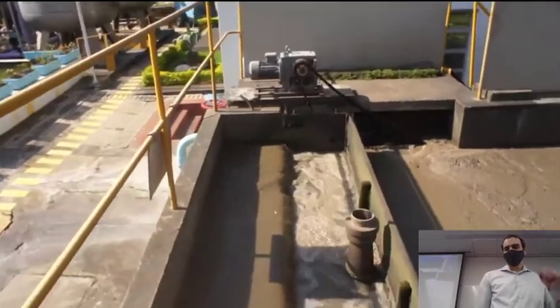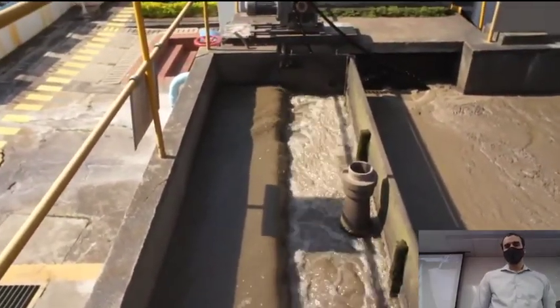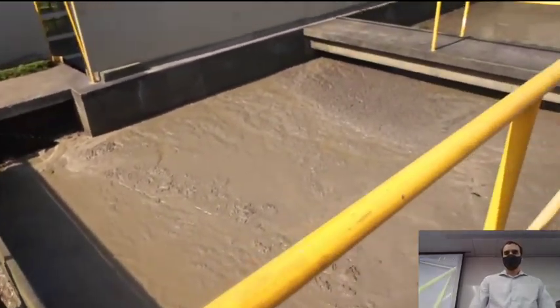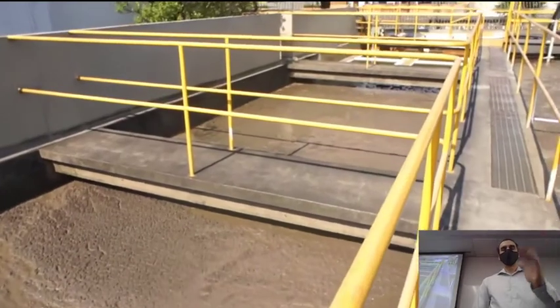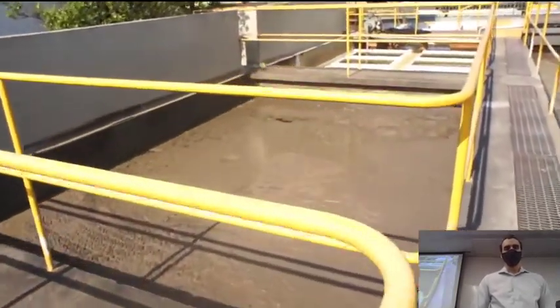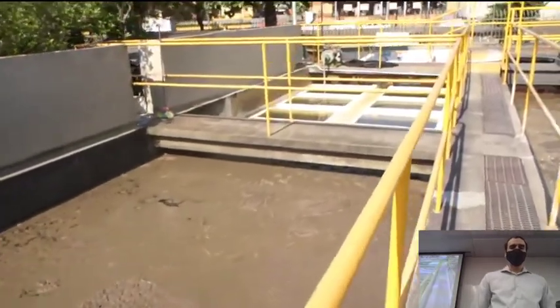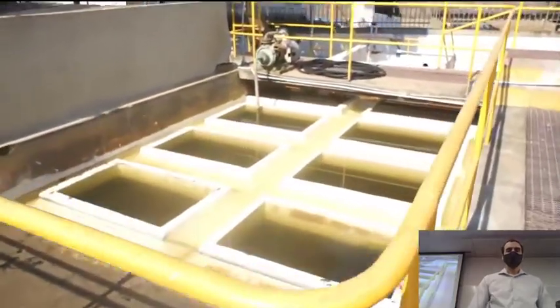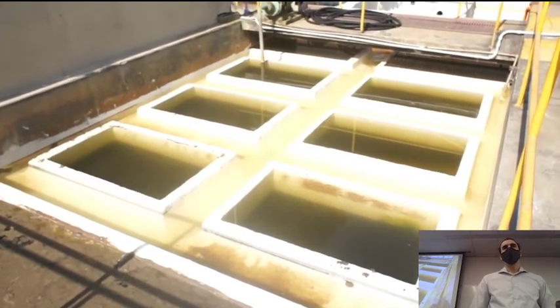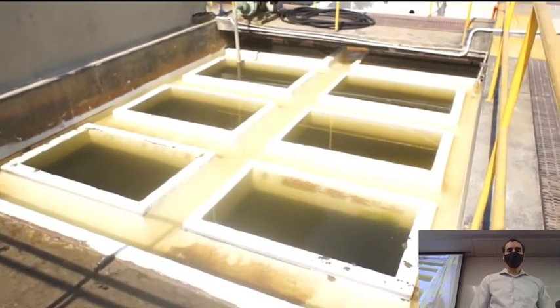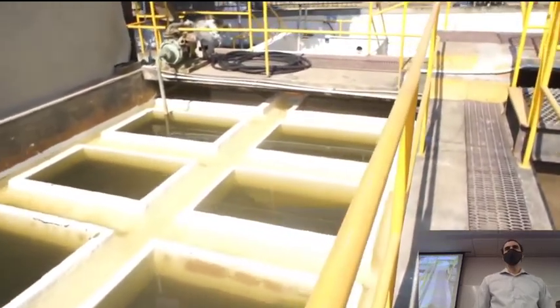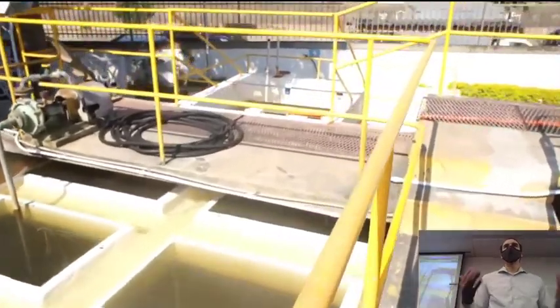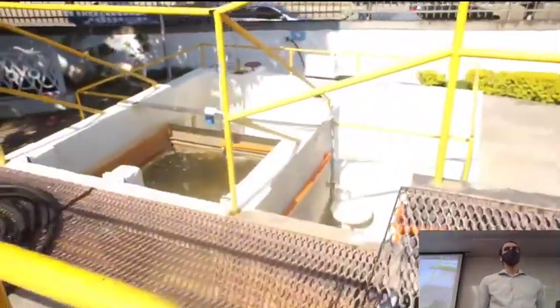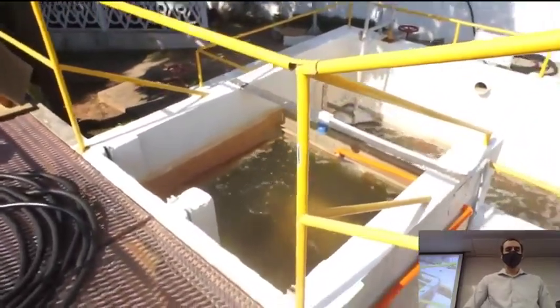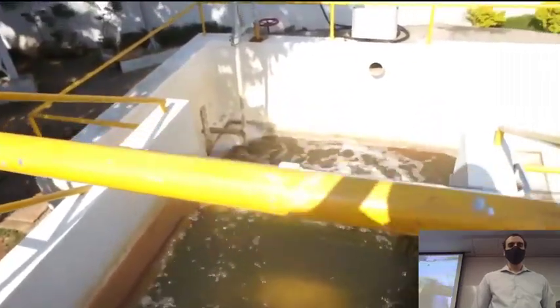moving on from there, these next steps may be another clarifier where you end up getting all the floating stuff at the top, and then the rest of the water is kind of moving slowly through. You can't see the motion because of the sludge, the foam layer, the scum layer. I think they probably have a way to harvest it and get rid of it. Sometimes you can actually operate sedimentation basins in reverse, where you add some very fine bubbles and cause things to float. Not large enough to cause mixing, but you can actually operate it that way on purpose sometimes. But usually it's common to have a sludge layer like that.